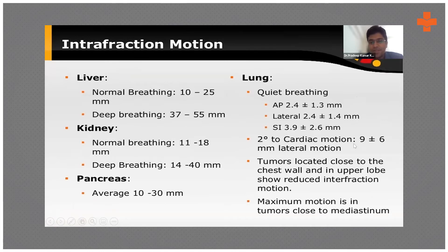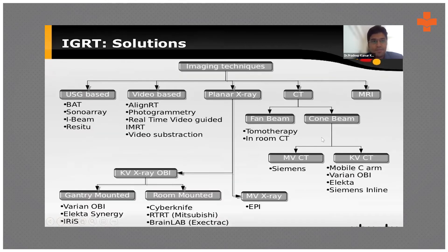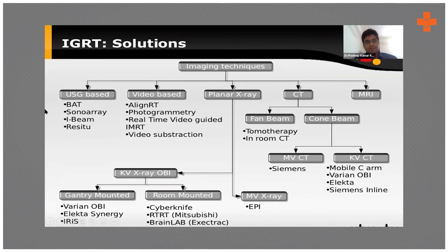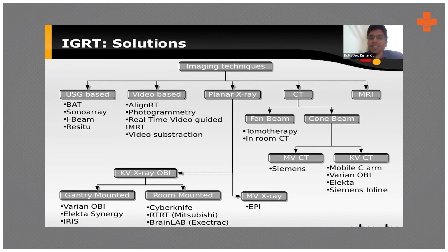These motion values help us correct geographical misses. As imaging techniques have advanced, their use with radiation has also increased. We can use ultrasound-guided, video-based, or X-ray-based imaging. With video-based systems, we use SGRT — surface-guided radiation therapy — which captures patient motion through sensors placed on the chest. This data is transmitted to the computer, which assesses how much the tumor is moving and adjusts the beam delivery accordingly so it precisely hits the target.